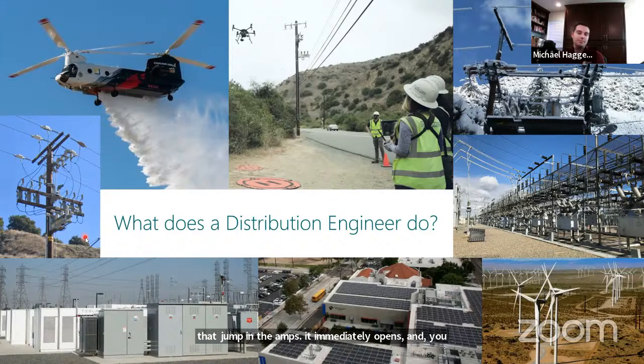Some other things we do are short circuit duty calculations. That means we calculate the fault duty at any given location. When new businesses interconnect to the grid, we have to perform that calculation for them so their equipment can be rated appropriately. Every county requires that.